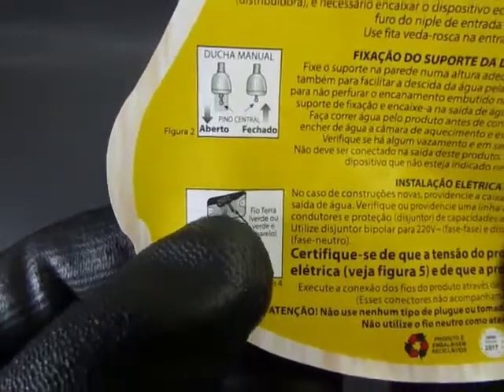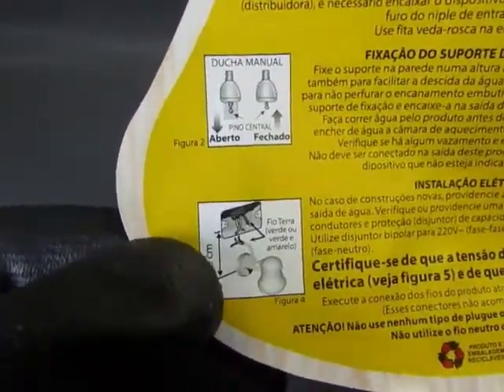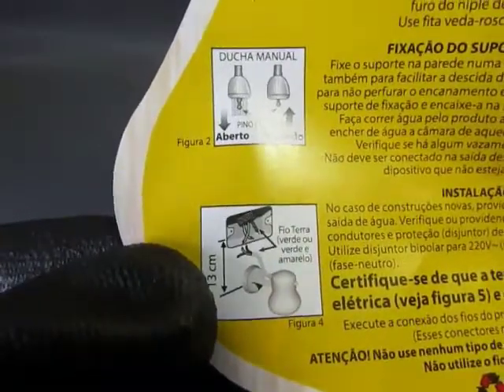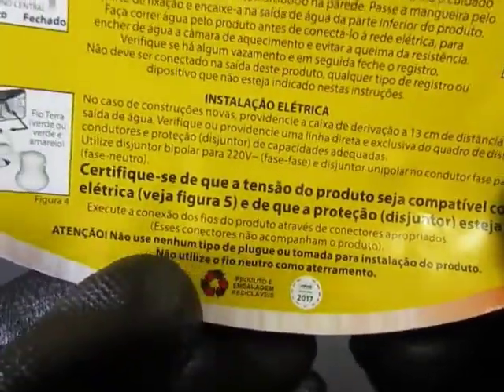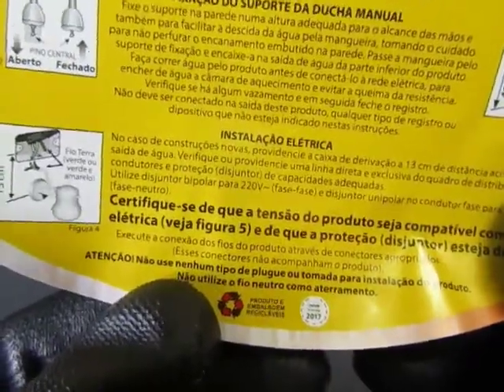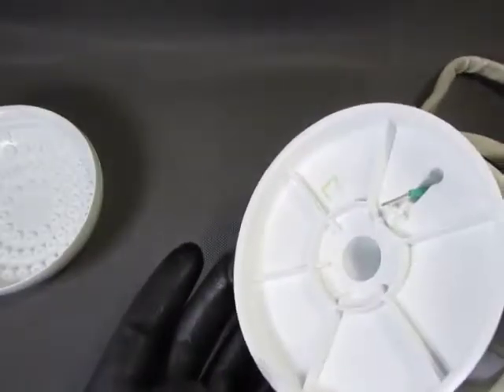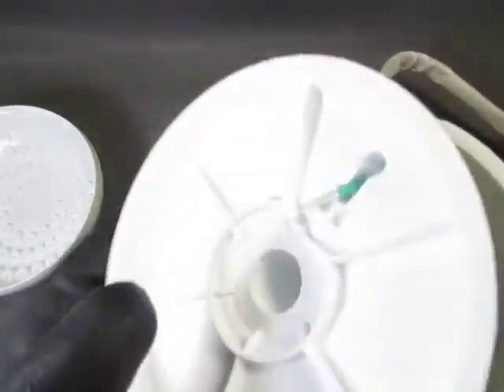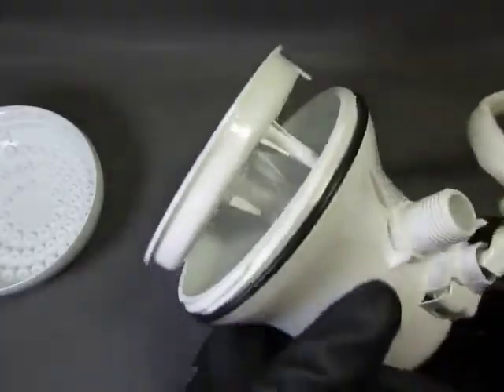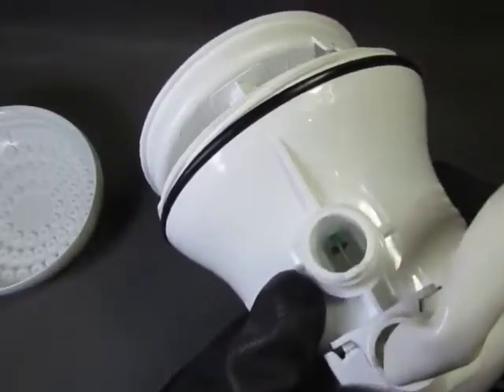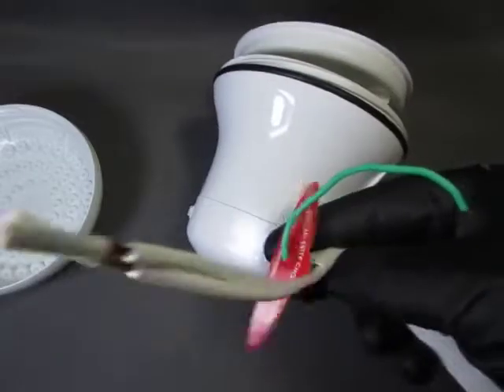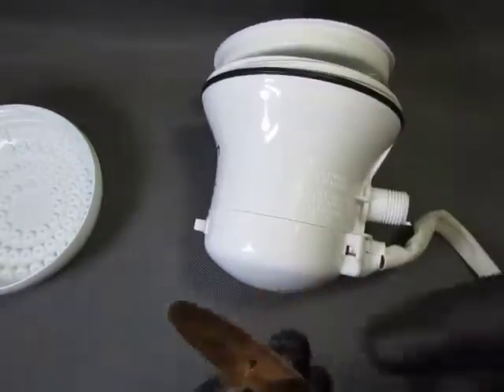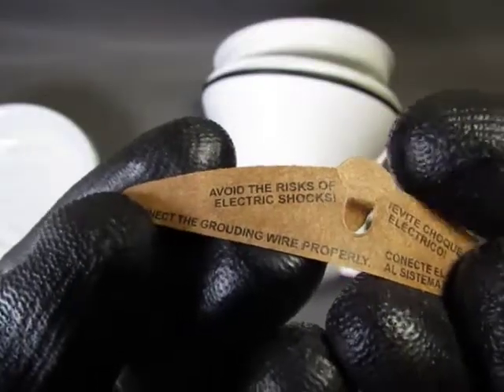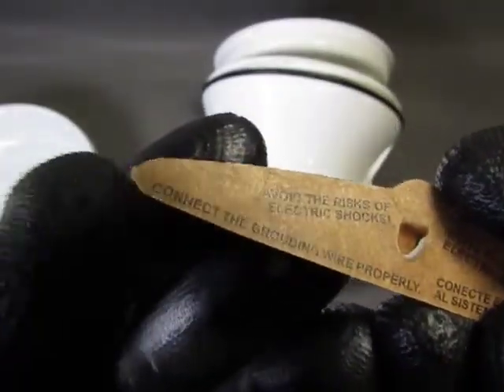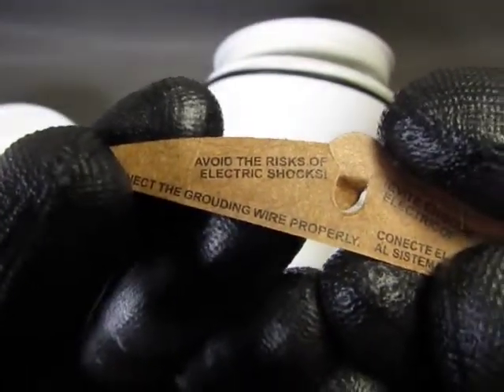Other recommendations are that the wires must come out of the wall at 13 centimeters above the water pipe and that no kind of power plug should be used. And finally, do not use the neutral wire as ground. So we have torn down the shower head and here we have the ground wire. It is made of copper, coated with something that is probably tin. This ground wire goes through here and also supposedly grounds the incoming water, and then it goes out through this bundling hose and ends on the other side with a sign that says, avoid the risks of electric shocks. Connect the grounding wire properly. I think you got the idea.